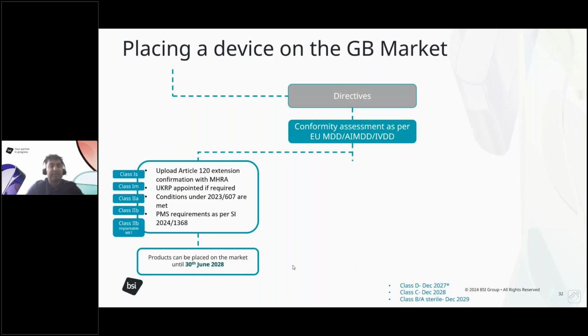So for the lower risk devices, the class 1S, class 1M, 2A, 2B, and 2B implantable wet devices, manufacturers can take on board the 2023-607 requirements and the timelines that have been addressed in Europe. So the MHRA have taken these on board. But you do require to upload an Article 120 extension confirmation to MHRA, appoint a UKRP if required, and make sure you are meeting the conditions under 2023-607, which Maddalena mentioned. In addition, from next week, the PMS requirements as per SI 2024-1368 have to be met. And then the products can be placed on the market until the 30th of June 2028, which are the timelines referenced in 2023-607 for these types of devices.